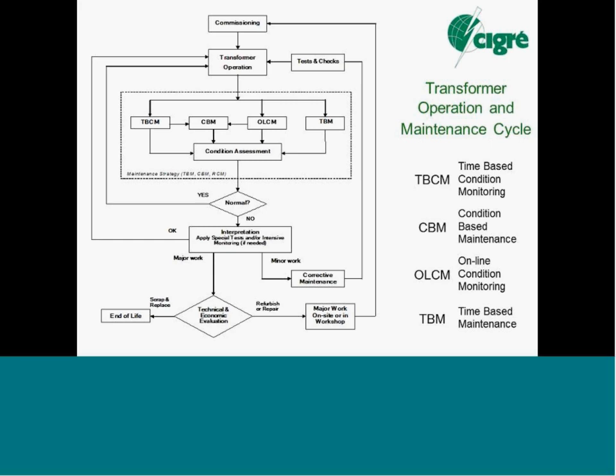we don't really jump into maintenance. Usually there's further interpretation, of the data that we're relying upon for action, but also sometimes extra special tests, or even some intensive online monitoring of the transformer to evaluate just how critical things are, maybe to narrow the cause of the problem to a particular area on the transformer. And of course that could return to normal, continued transformer operation. Usually through that interpretation we identify whether we have minor work or major work.